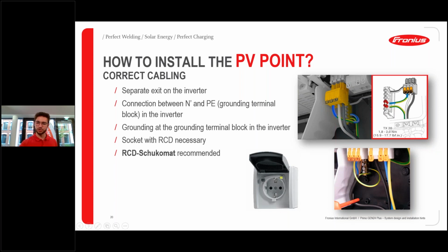And the reason for this short bridge here to the grounding terminal block is because we need to create our own PEN conductor. Because in the grid outage we are gone, so there is no grid parallel mode anymore, and the PV point, in order to operate well, needs to have a PEN conductor here, and this is why we have to do this cabling like that. So just remember, the 3 cables don't go directly into the PV point, only neutral and phase, and the grounding cable is going first to this grounding terminal block and then up to the PV point.